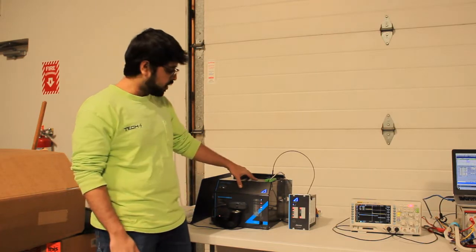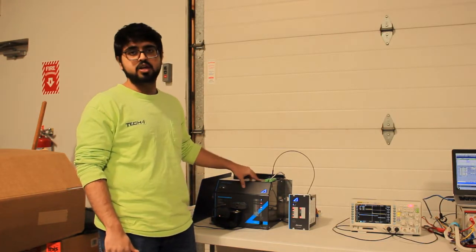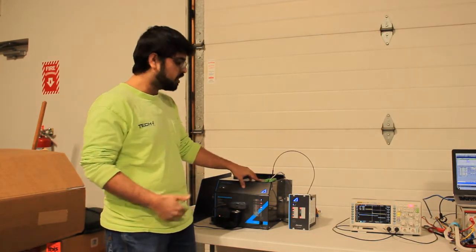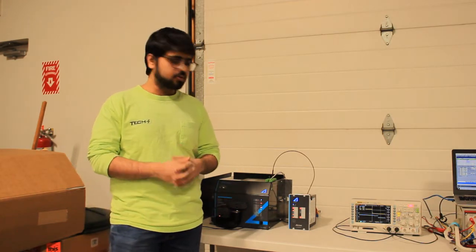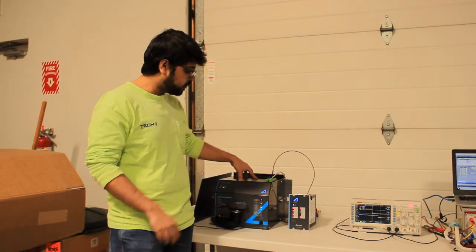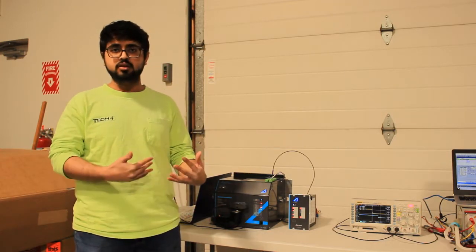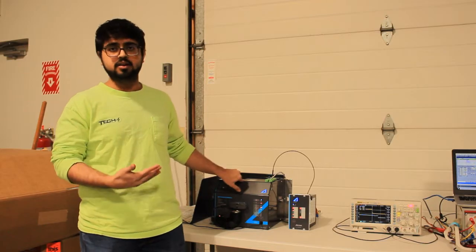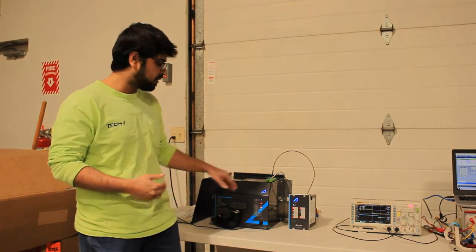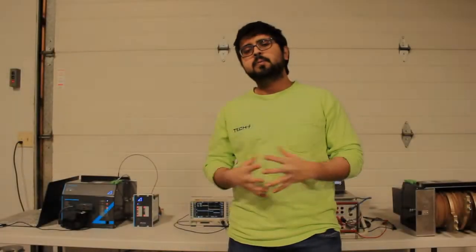So Arteche has built in a commissioning mode which is used for testing. The AQ-1000 knows it's not under load and it's not in use, so it bypasses the trip count. So that was a demonstration of how to time test an arc quencher, and that's how we do it here at Tech Four.